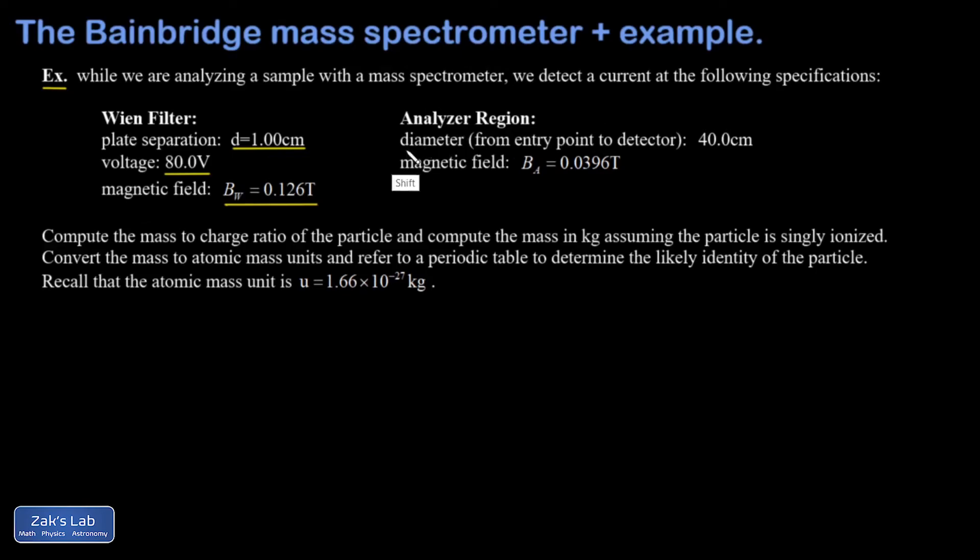In the analyzer region, we have a diameter from the entry point into the analyzer all the way down to the detector. Again, this is a semicircle of 40 centimeters. And that means the radius of curvature is 20 centimeters for any beam that's going to be detected. And we have a magnetic field in the analyzer region of BA is 0.0396 Tesla.